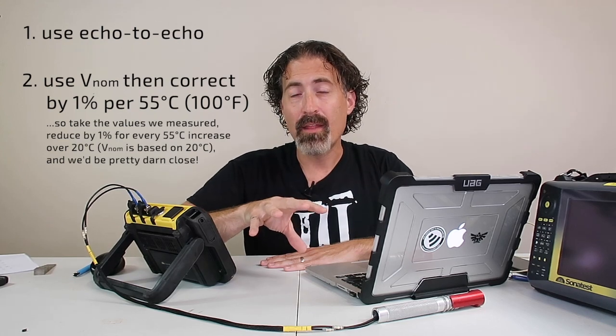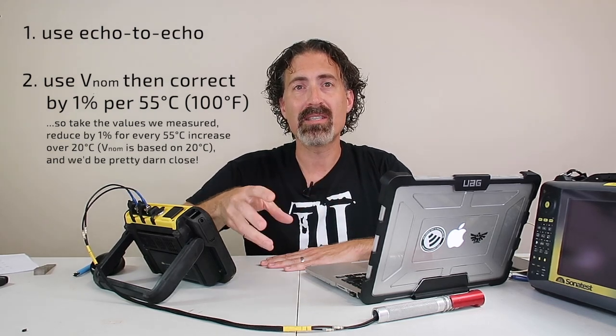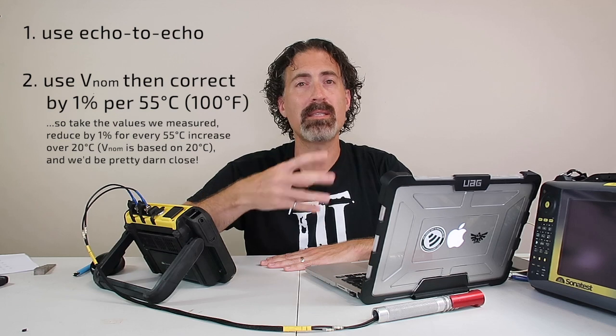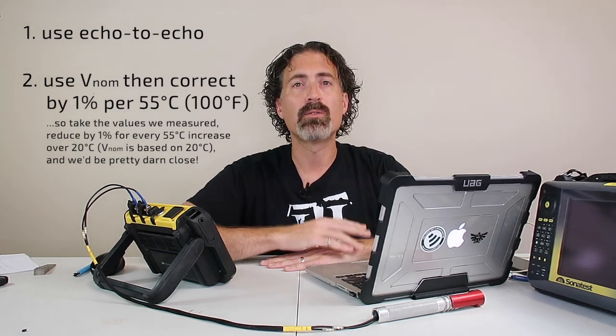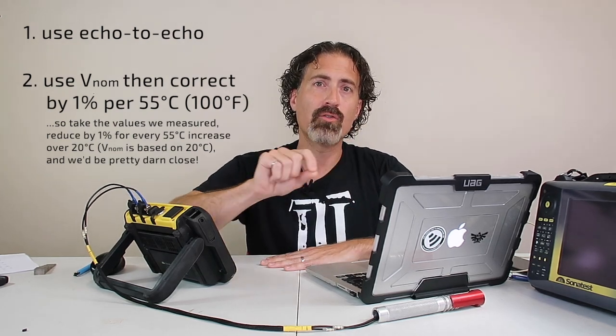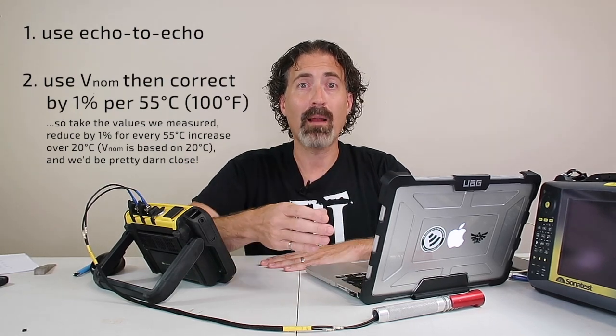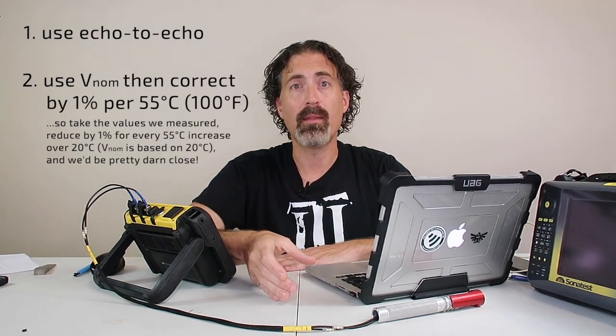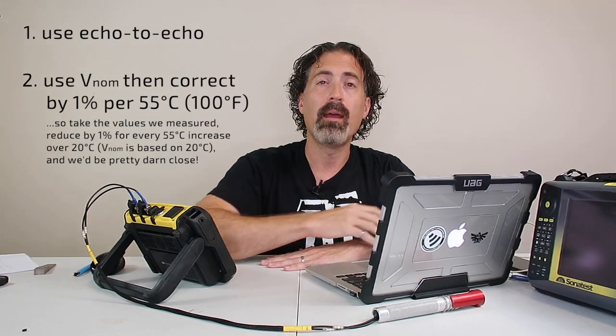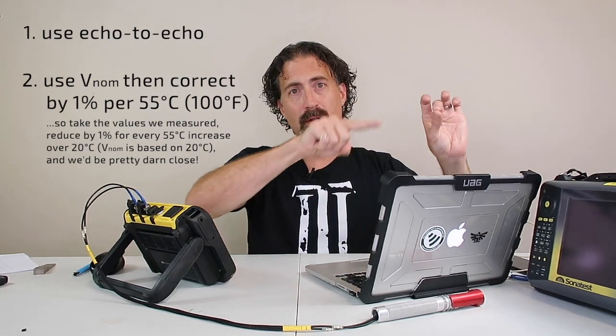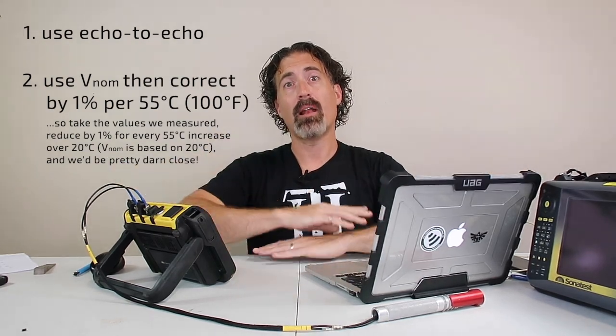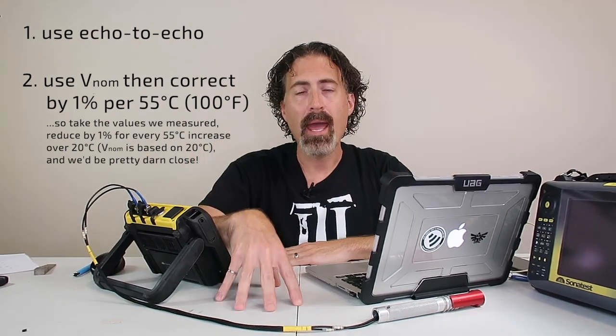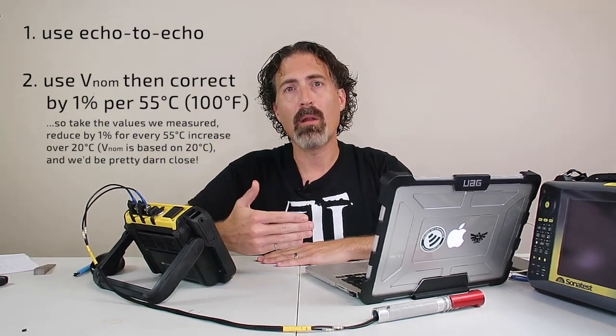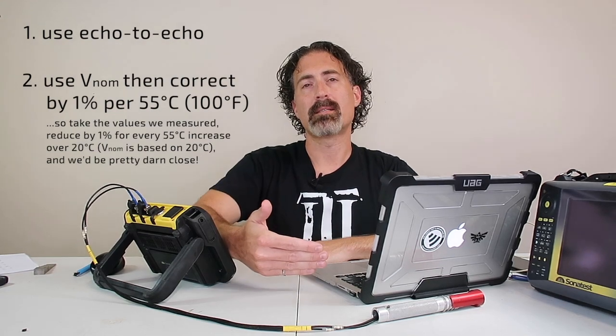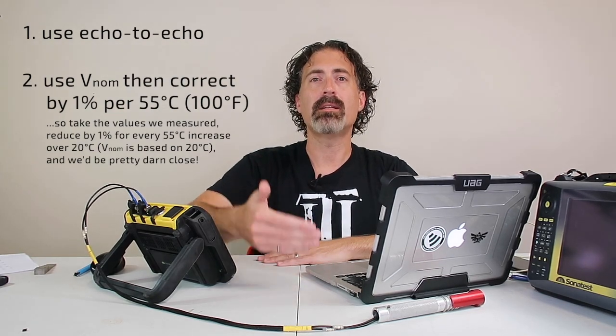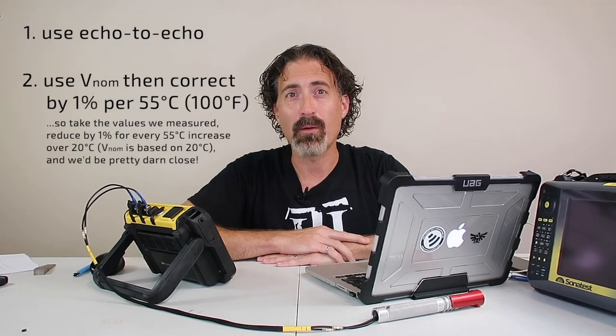You can. The thing is that it will be very inconsistent between groups of people, and when you're doing CMLs or TMLs, whatever you call them, it's really important to maintain a good trend. If you try to calibrate on a hot block and you do it one way and the other person does it another way, what's going to happen is that chart over time, as they're trending the thickness of that location, is going to be all over the place. And it also won't heat the cal block up to the process side of the material. It will only heat it to the outside because you're on the outside taking readings, aren't you?